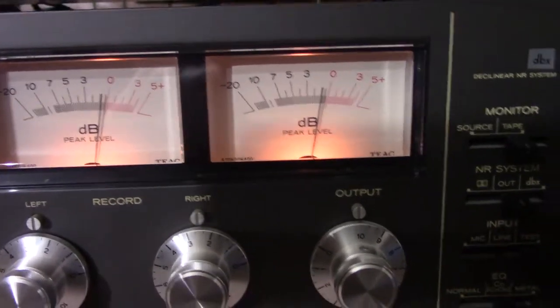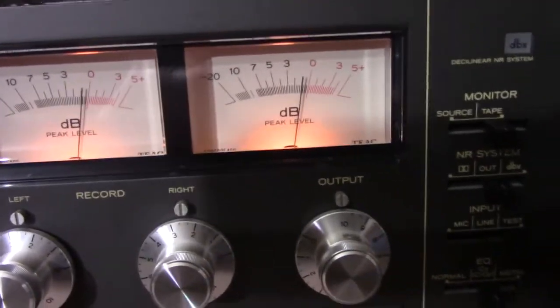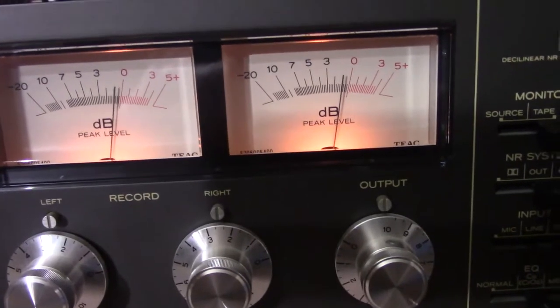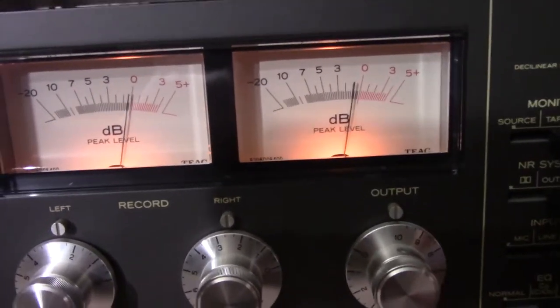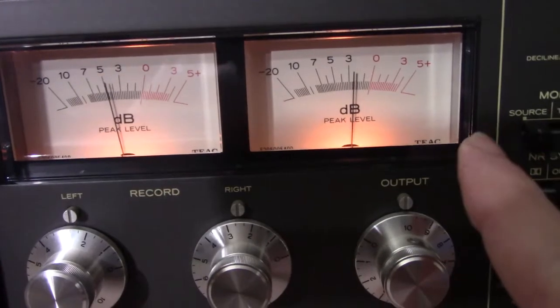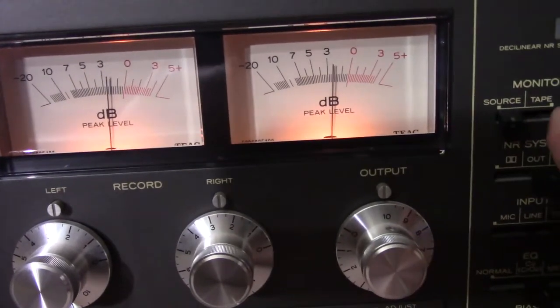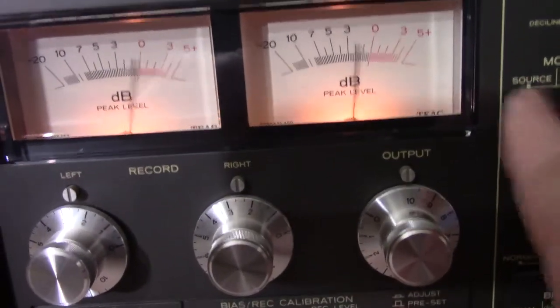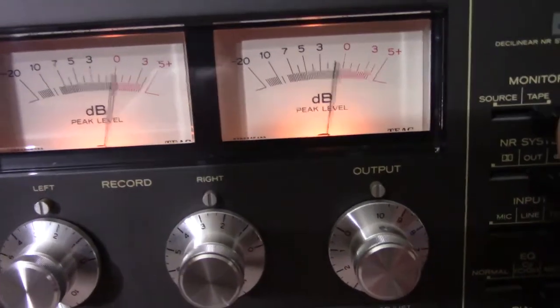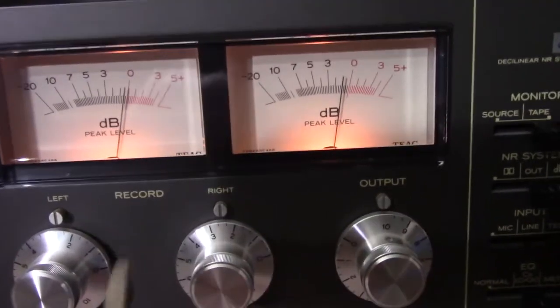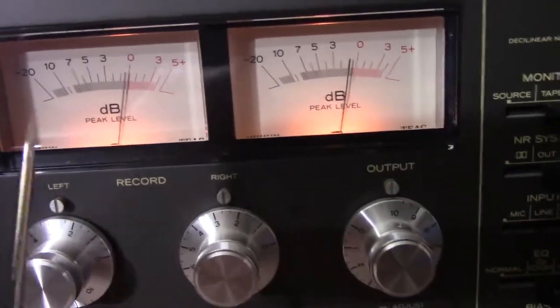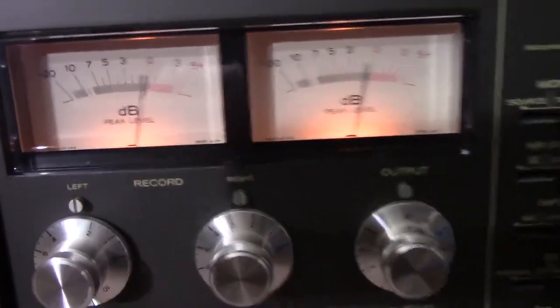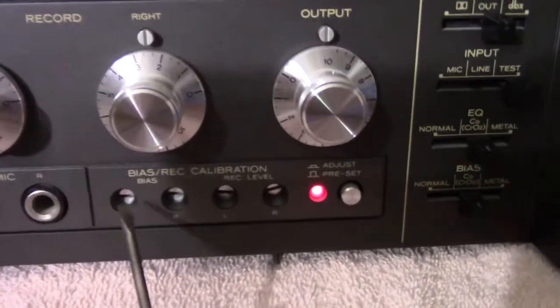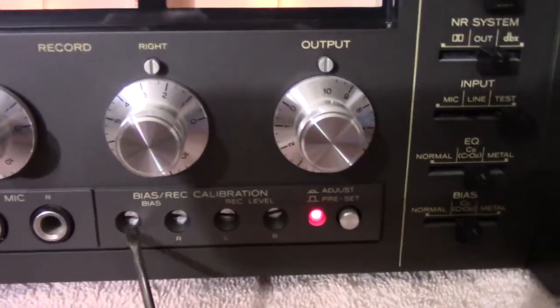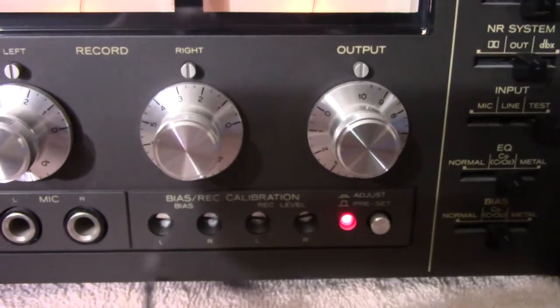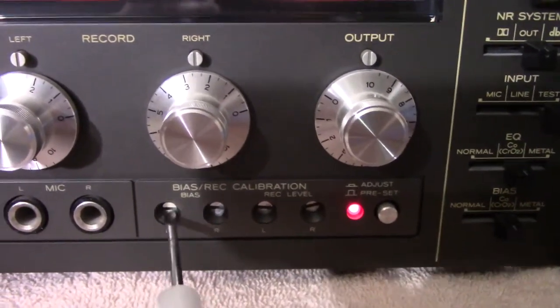Okay, and you see that's the point where I had it calibrated before, and that is what you're expected to do. You get the levels so that, at least when they're playing back on the tape, they're the same reading. And that's what we've got here. How you do that is through these adjustments here. And just to show you what it is to do it, I'm going to put this one out of calibration and bring it back in.